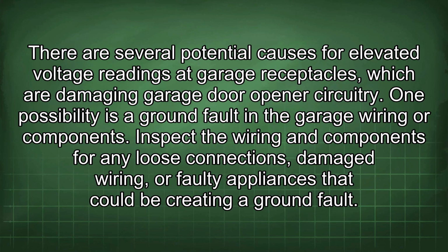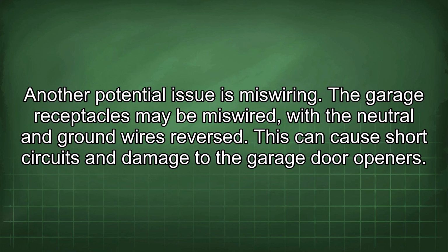There are several potential causes for elevated voltage readings at garage receptacles, which are damaging garage door opener circuitry. One possibility is a ground fault in the garage wiring or components. Inspect the wiring and components for any loose connections, damaged wiring, or faulty appliances that could be creating a ground fault.